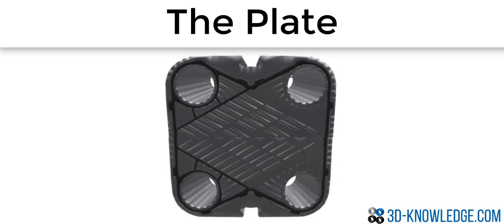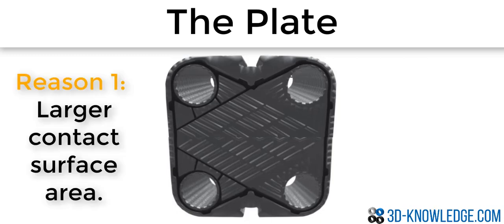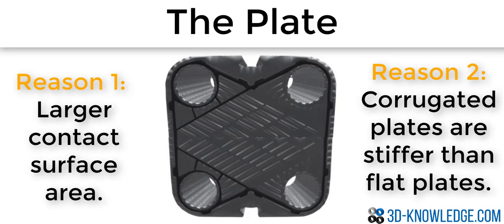You may have noticed that the plate isn't flat — it's actually corrugated. The reason for this is threefold. First, a corrugated plate gives a larger contact surface area, which increases the heat transfer rate and makes the heat exchanger more efficient. Second, a corrugated plate is actually stiffer than a flat plate, so you can manufacture a thinner plate, and a thinner plate has a higher heat transfer rate than a thicker one.